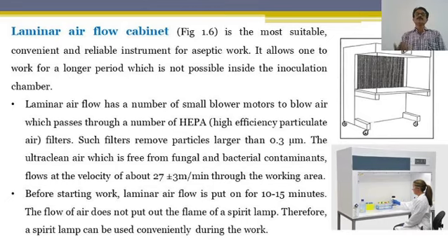So keep in mind that before starting this laminar airflow, you need to switch on its UV light 10 to 15 minutes prior, so that whatever contaminants or microbes are there get killed. And then you have to swab it with alcohol and cotton to remove the dust particles and other contaminants from the floor of the laminar airflow.